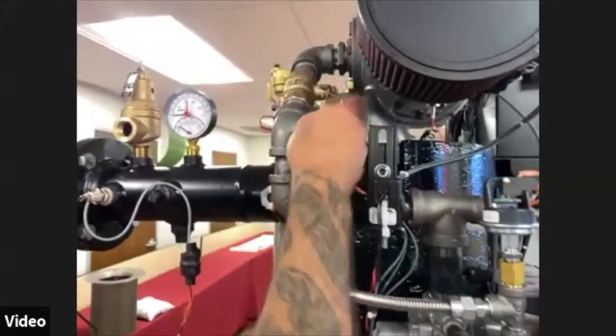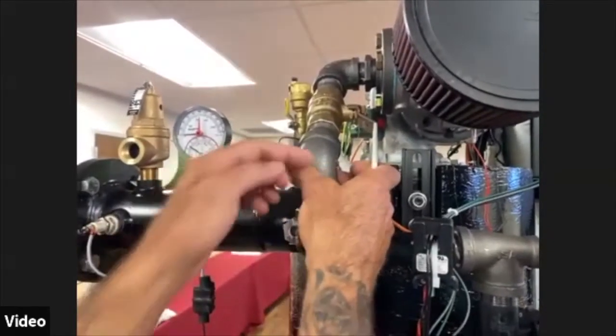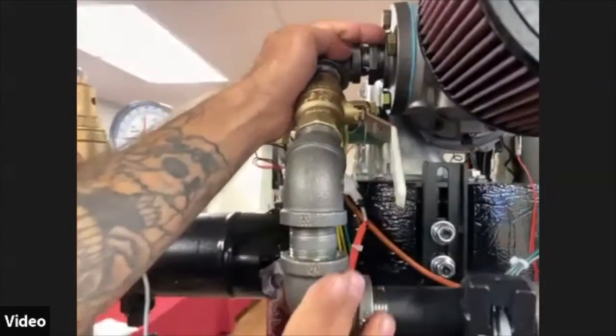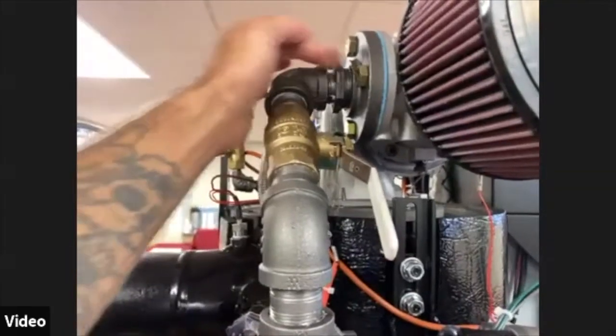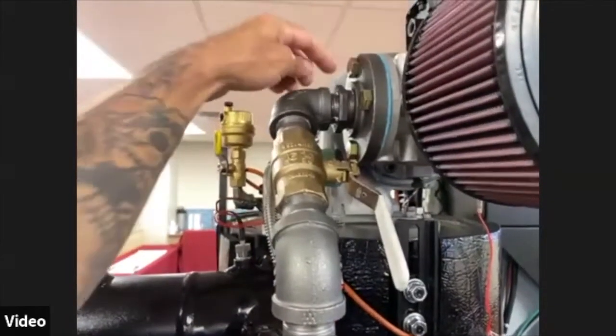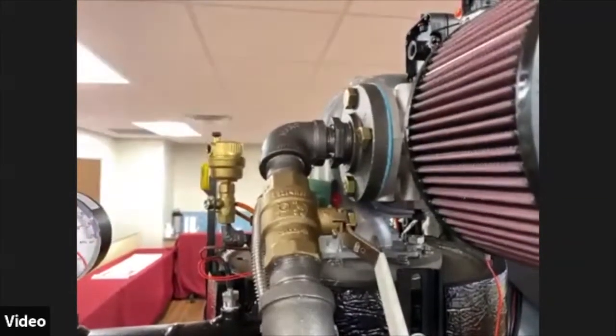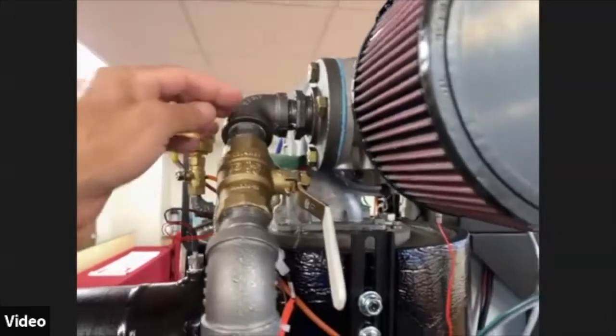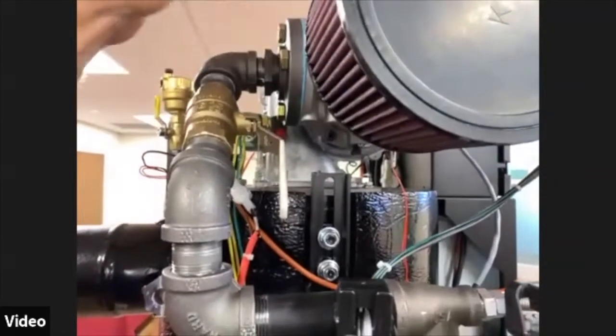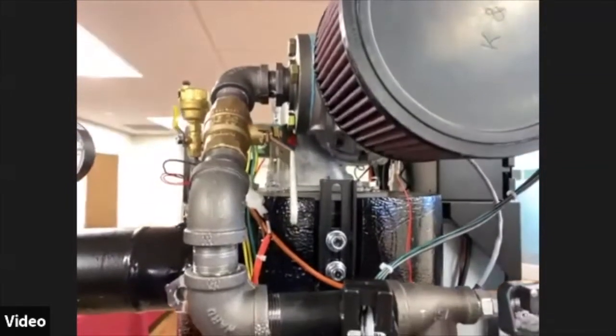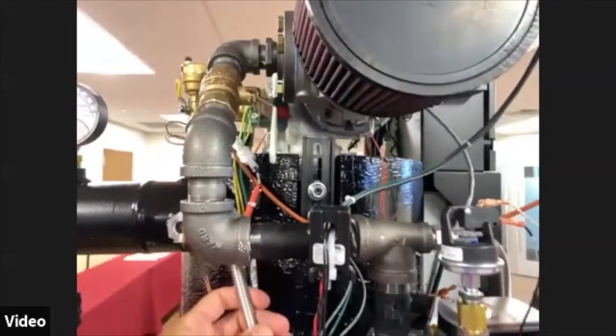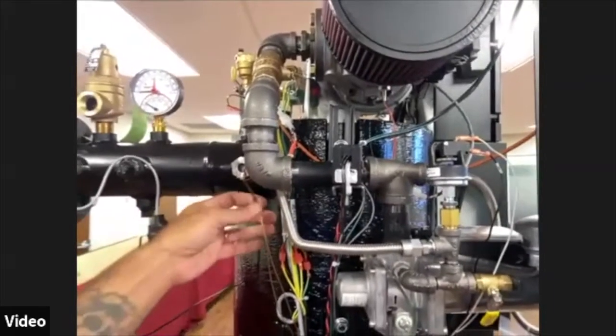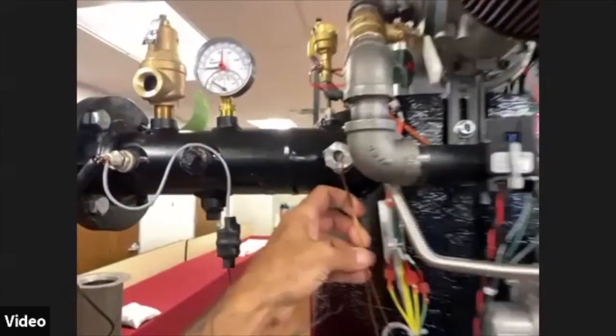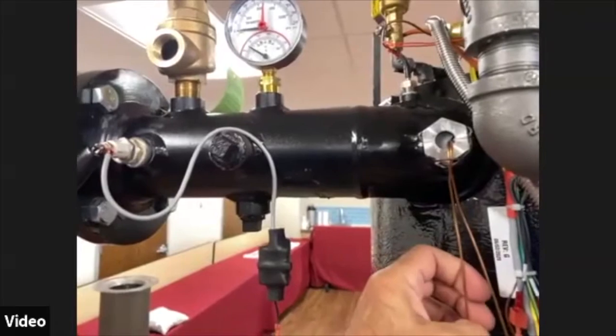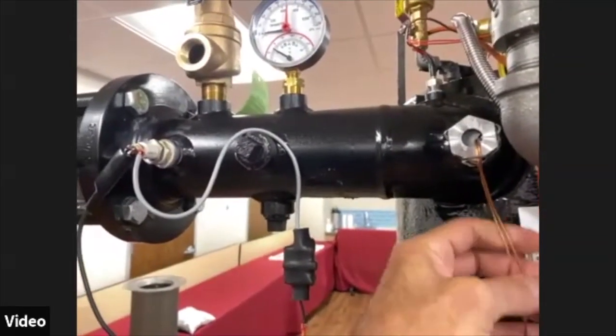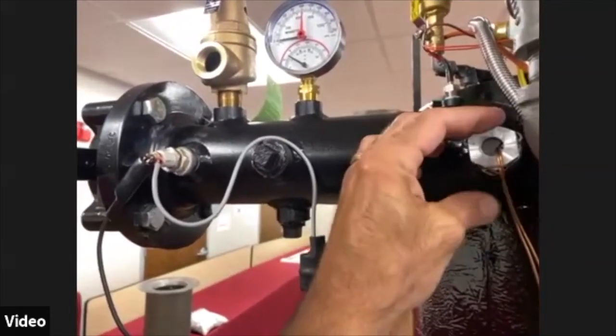This would be our internal gas shutoff supplied by the manufacturer, and this comes into the other side of the air fuel valve. So we have the air coming in here, and we have the gas coming in here, mixing together, going through our blower, which we'll take a look at when we get around the other corner. You'll be able to see that a little bit better. Pre-mixed down into our fiber mesh burner. This would be our dual temperature sensor. So our manual reset and our operating limit are both tied into this particular well here.